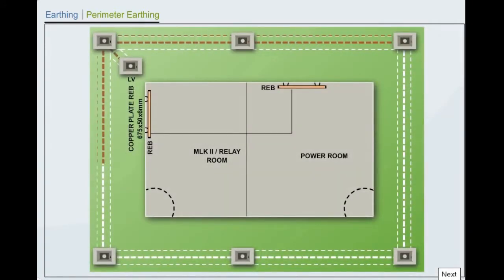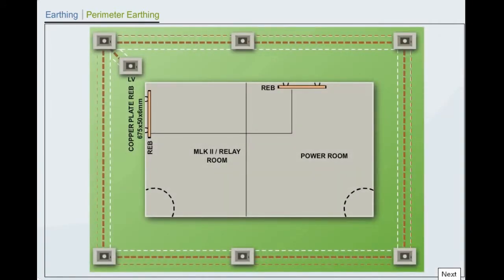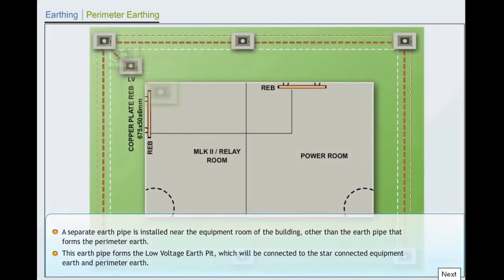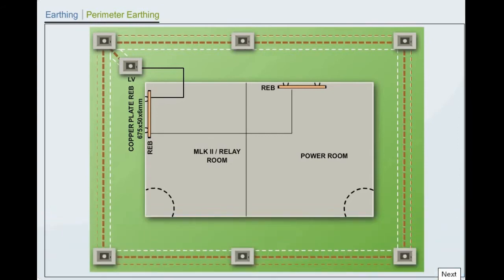Earth pipes installed along the perimeter of the equipment room and power room must be coupled together to form the building perimeter earth. A separate earth pipe is installed near the equipment room of the building, other than the earth pipe that forms the perimeter earth. This earth pipe forms the low-voltage earth pit, which will be connected to the star-connected equipment earth and perimeter earth. The low-voltage earth pit to room earth bar is connected with 2 by 16 mm standard insulated copper wires.